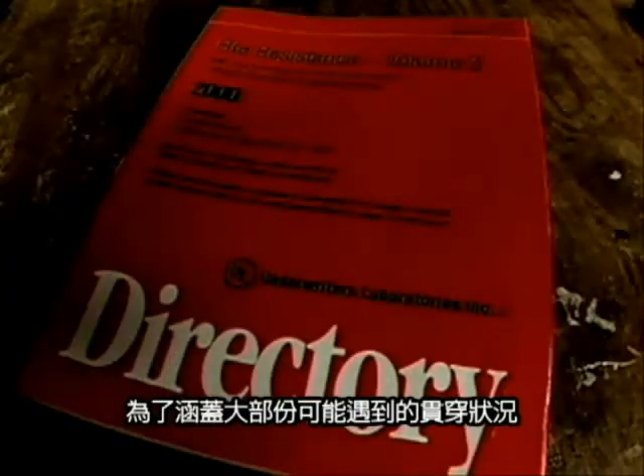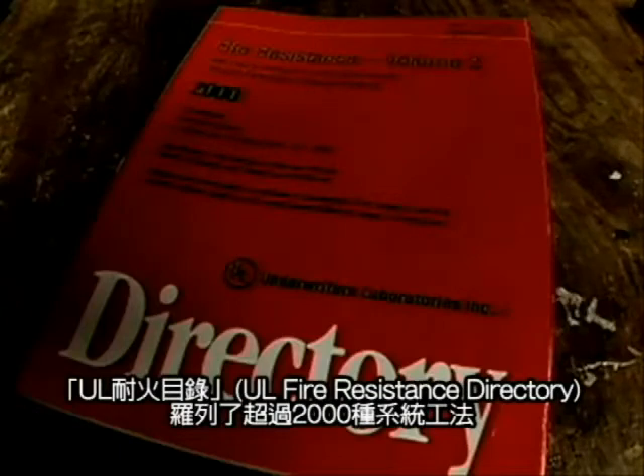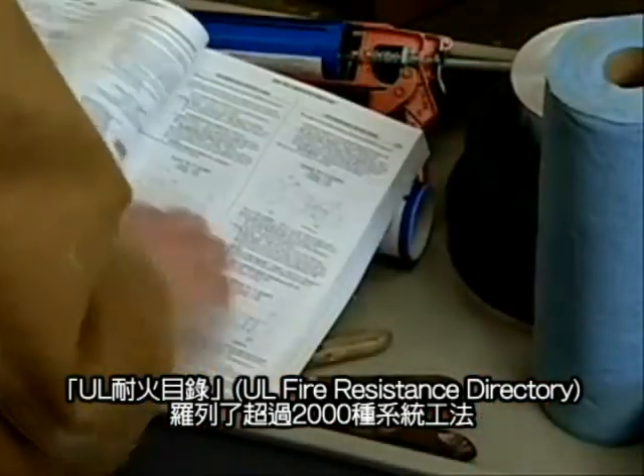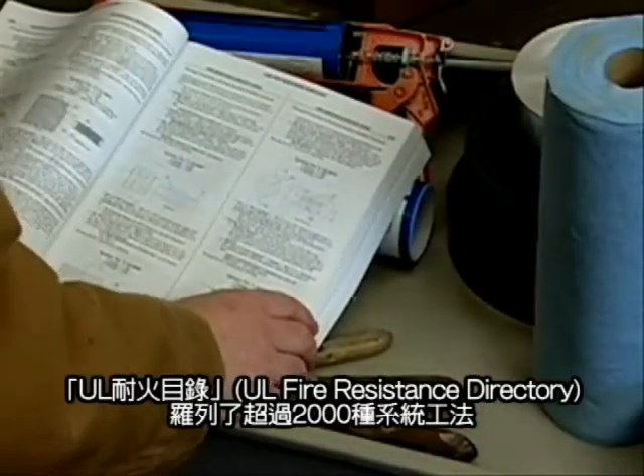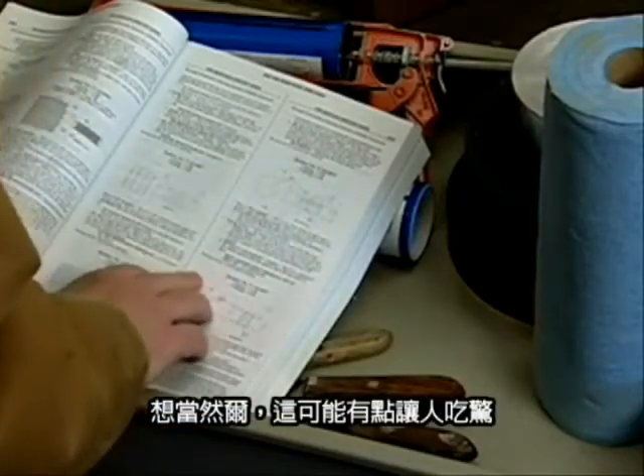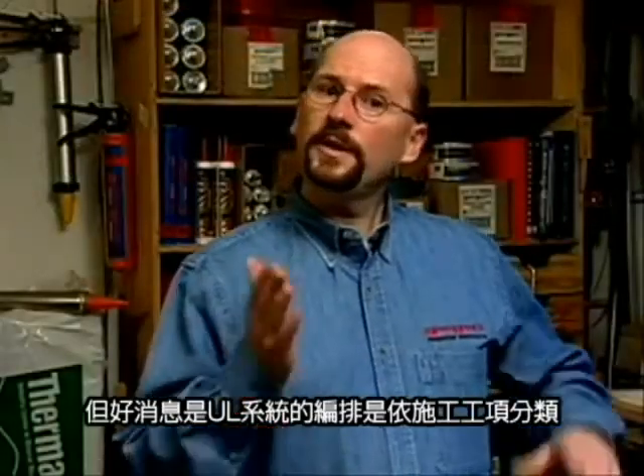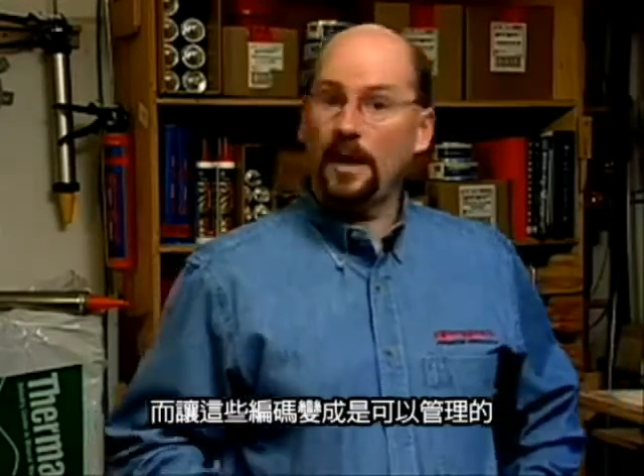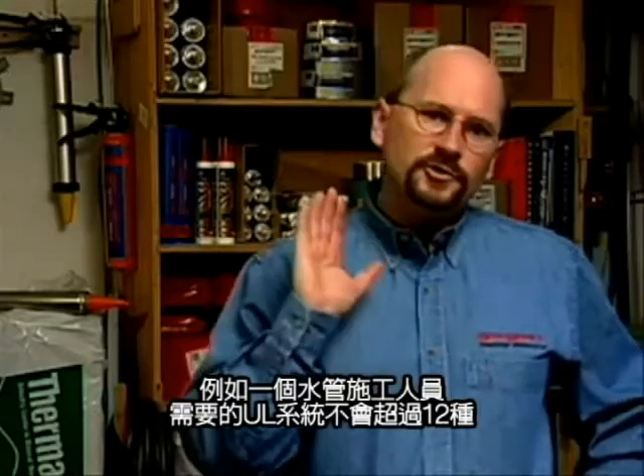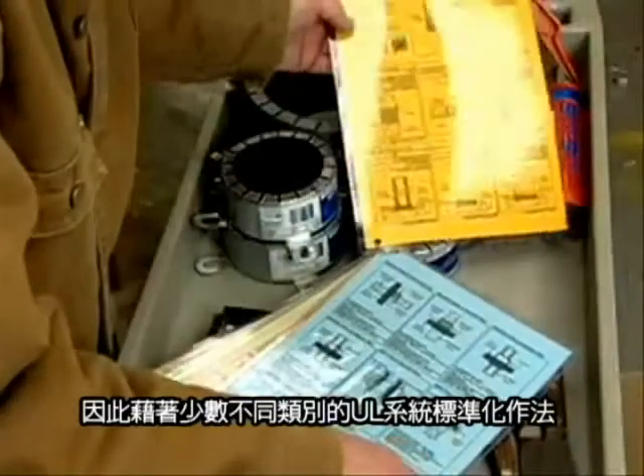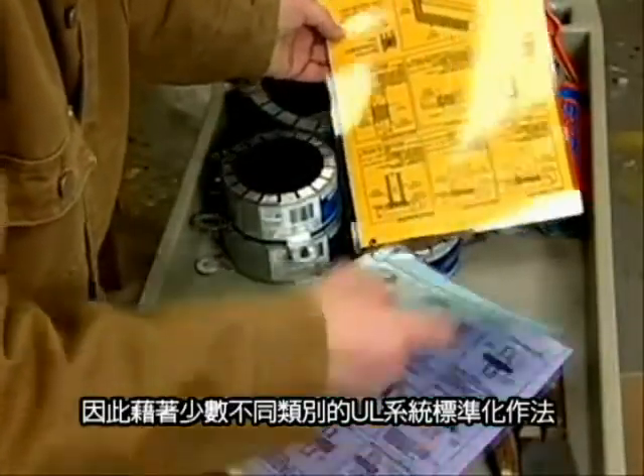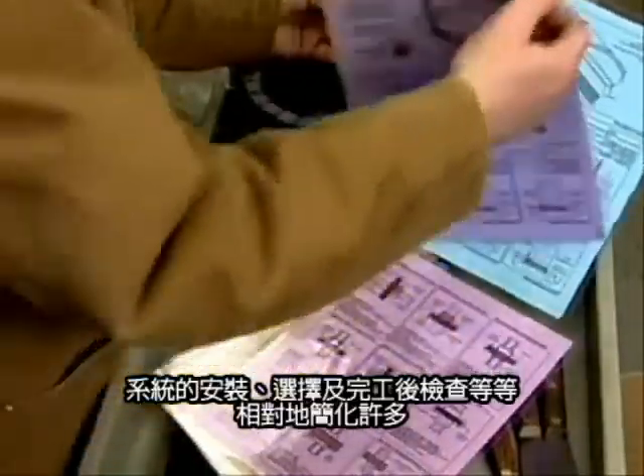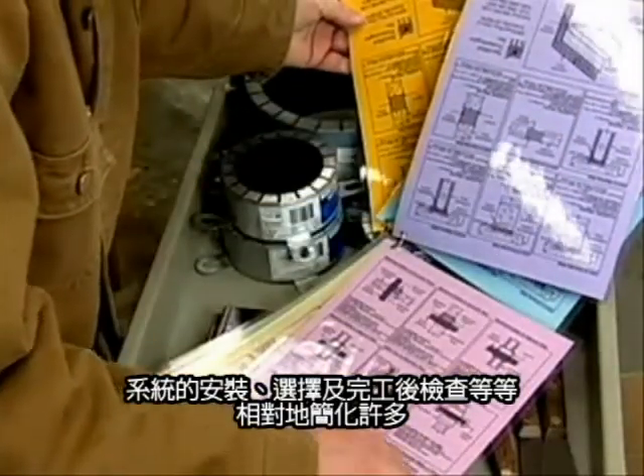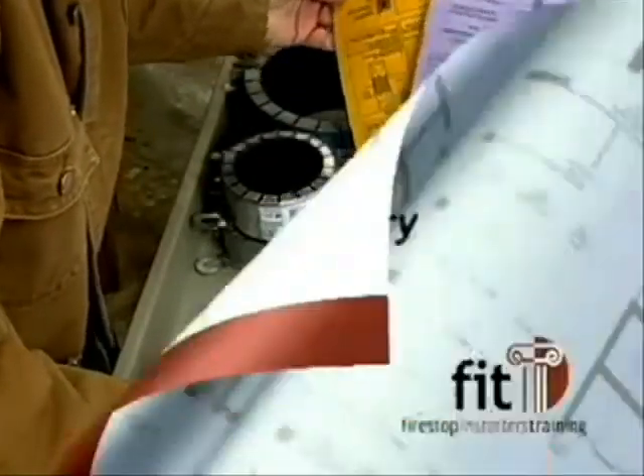To help address most every condition that you will encounter, the UL Fire Resistance Directory contains more than 2,000 listed systems, which quite understandably can be a bit overwhelming. But there is good news. When the number of UL systems is broken down by craft, the number becomes manageable. A plumber, for example, typically needs less than a dozen UL systems to address nearly all plumbing penetrations. Therefore, by standardizing on a few UL systems, installation, system selection, and inspection of completed work is dramatically simplified.